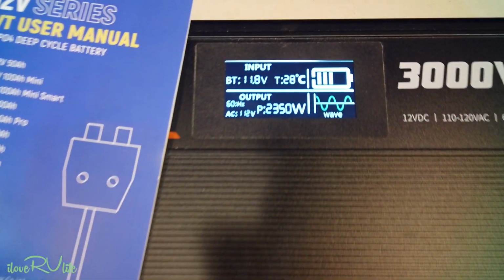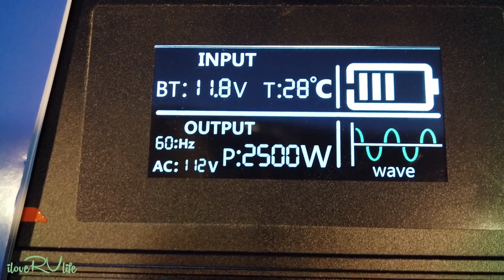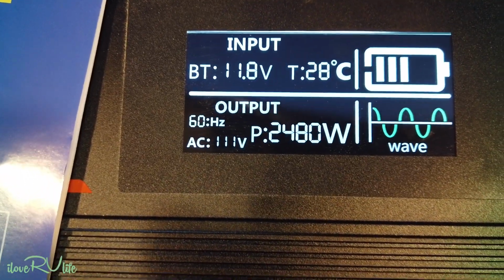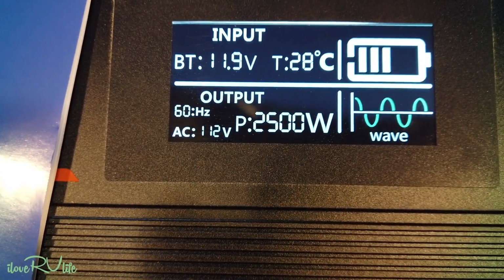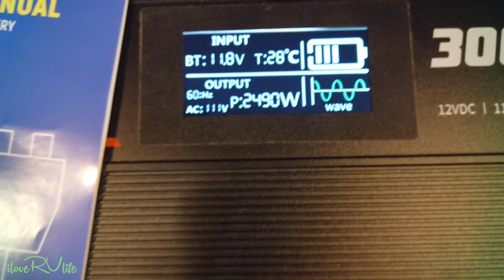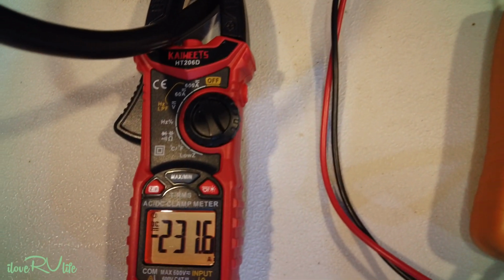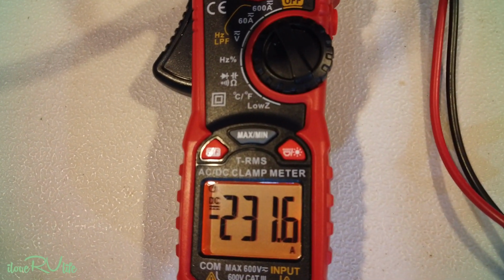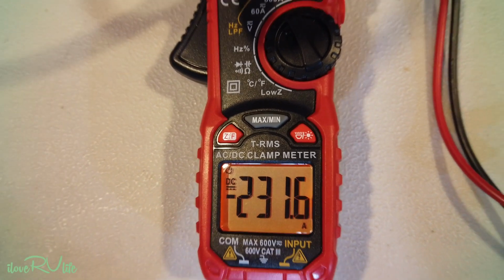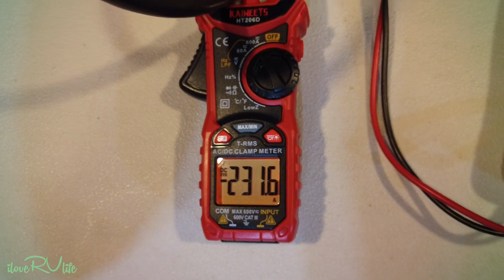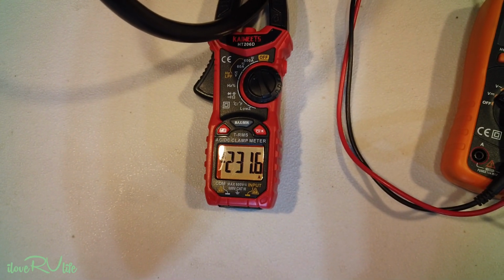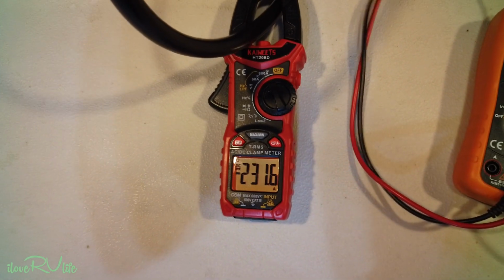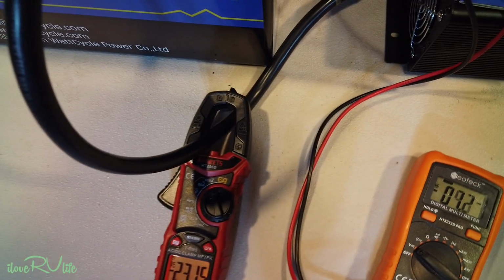Here's where we should trip it out. We are now at 2,500 watts, bouncing back and forth, and this BMS, as I typically see in most of these BMSs, will go over the 200 amps. I mention this often: if you have a 200 amp BMS, fuse it at 200 amps for this type of thing. Let's see how the battery is performing voltage-wise.